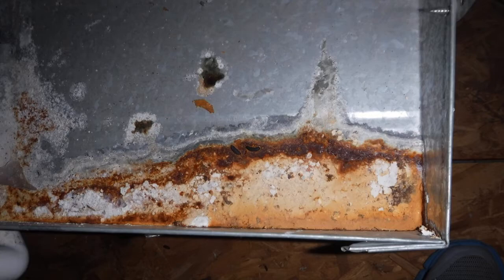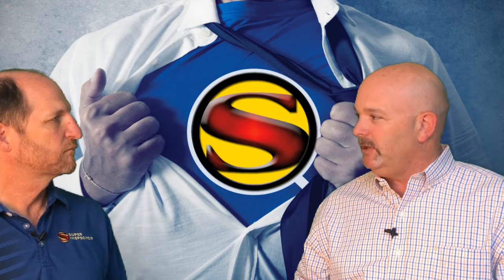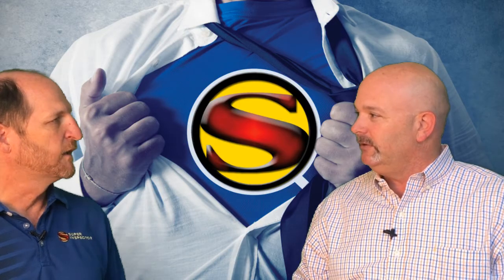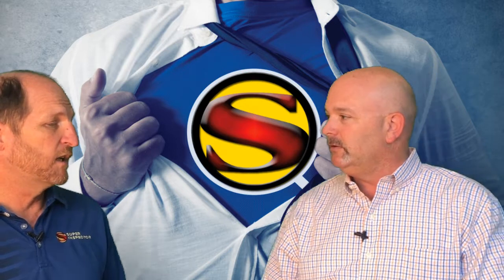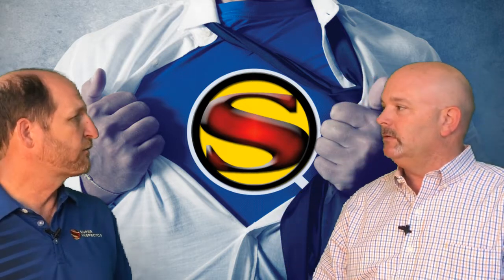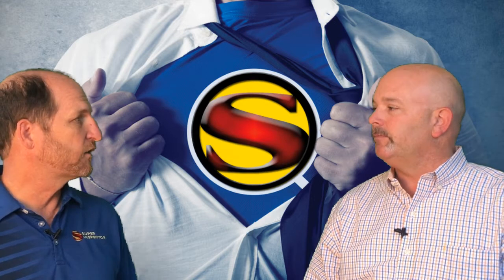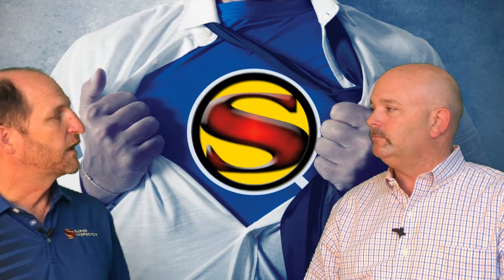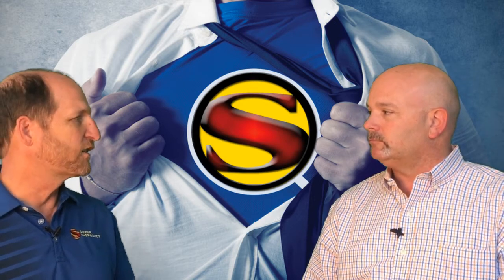And that water stays there forever until it dries up, and then it causes the rust. Right. And a lot of that can just be condensation dripping off the refrigerant pipe into the pan under normal operation. Yeah. So that pipe needs to be insulated to help prevent that.